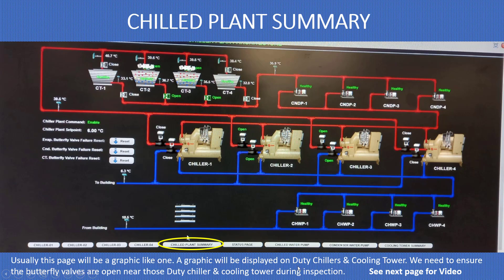The plant schematic page shows a graphic of the plant room — the chiller plant schematic. This graphic displays the duty chiller and cooling tower. During inspection, ensure the butterfly valves are open near the duty chiller and cooling tower. You can see there are four chillers and four cooling towers. Chilled water comes from the buildings through the chilled water pumps. This system has one chilled water pump per chiller — no primary-secondary configuration. There are four condenser pumps, each chiller dedicated to one cooling tower, one condenser pump, and one chilled water pump.